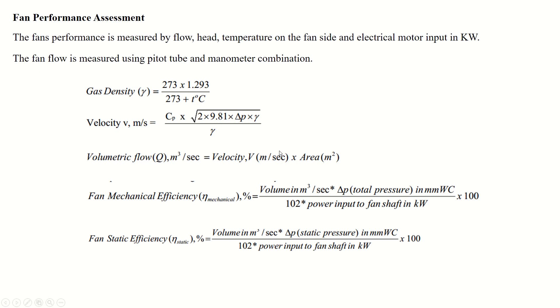Fan performance can be measured by flow, head, and temperature measurement on the fan side, and electrical motor input measurement on the motor side. Fan flow is measured using a Pitot tube and manometer combination. The formula for air density calculation is given in equation number one, and the velocity of air in a duct or pipe can be measured using the second formula.